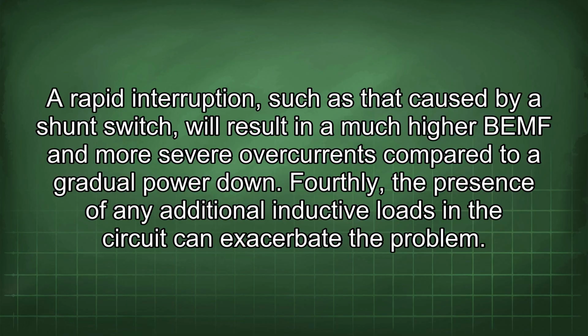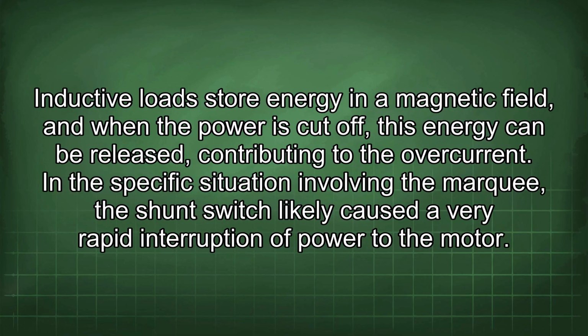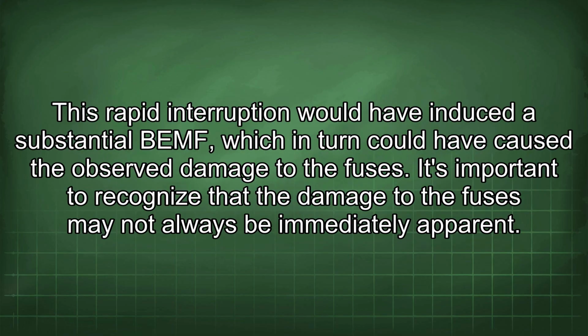Fourthly, the presence of any additional inductive loads in the circuit can exacerbate the problem. Inductive loads store energy in a magnetic field, and when the power is cut off, this energy can be released, contributing to the overcurrent. In the specific situation involving the marquee, the shunt switch likely caused a very rapid interruption of power to the motor. This rapid interruption would have induced a substantial BEMF, which in turn could have caused the observed damage to the fuses. It's important to recognize that the damage to the fuses may not always be immediately apparent.